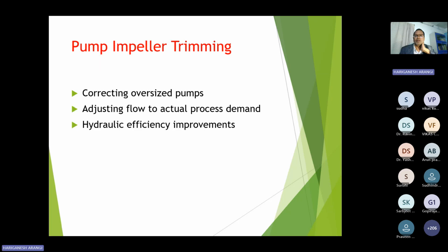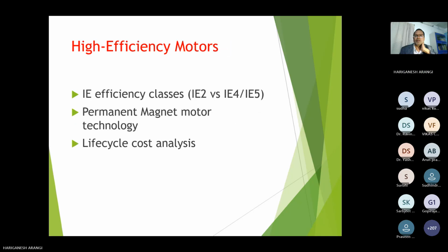Yeah, pump impeller trimming. After some intervals of usage, there will be erosion, so the impellers will be regularly checked, and they will be modified or retrofitted. And more, by using high efficiency motors like IE4, IE5. Earlier they used to run as IE2, IE3, but gradually they are being replaced with IE4, IE5. These are high efficiency motors where the losses will be less.